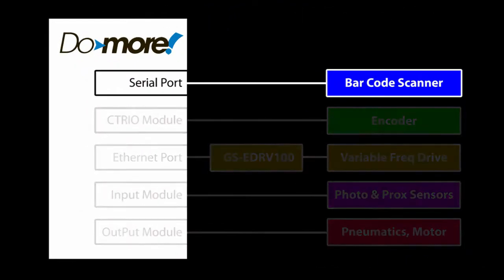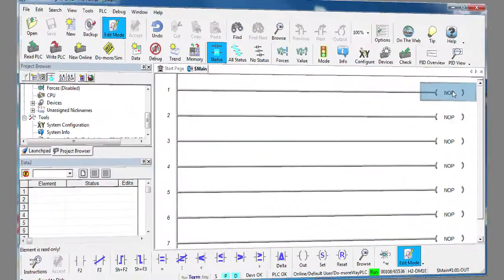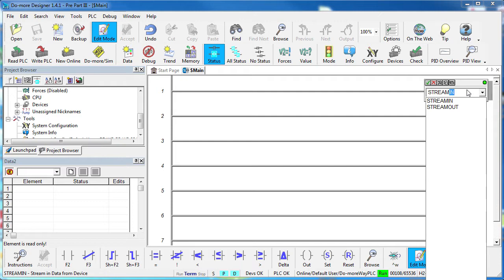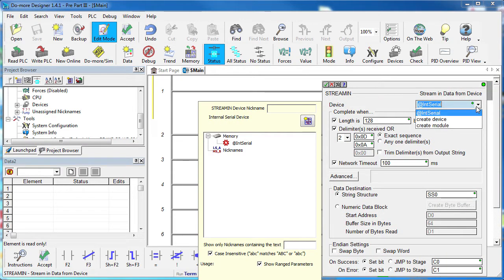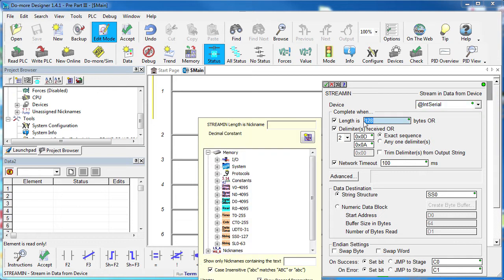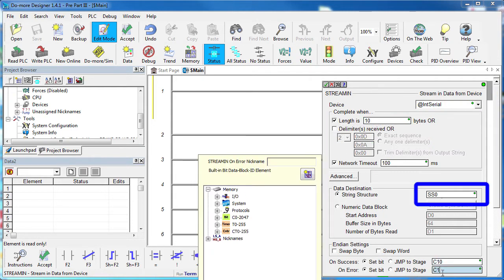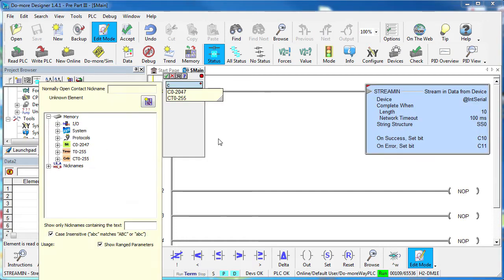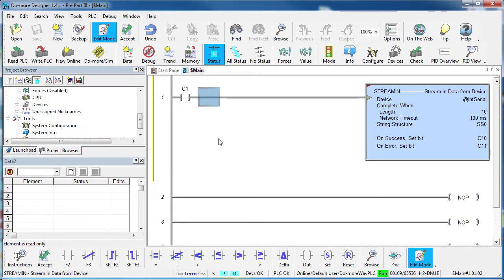Let's start with the barcode scan on a serial port. Because this serial port device takes care of all the details, all you have to do is use the serial port stream in instruction. Select the internal serial port device that we configured, specify how each string is terminated and pick a place to put the result. This instruction needs to be triggered so we'll add a contact to do that.